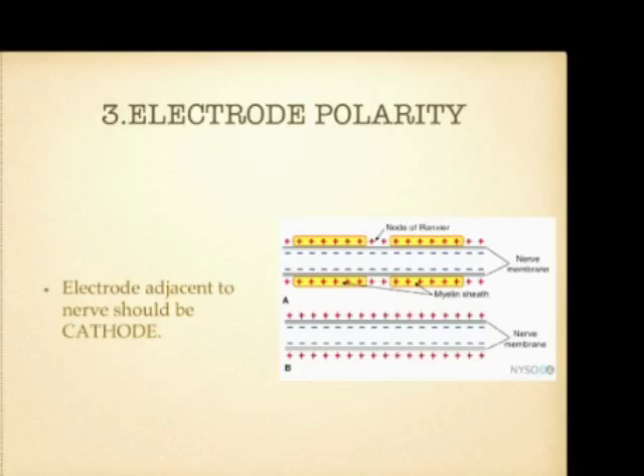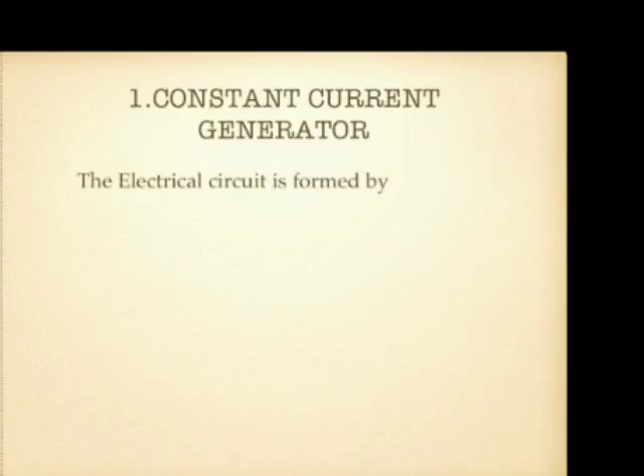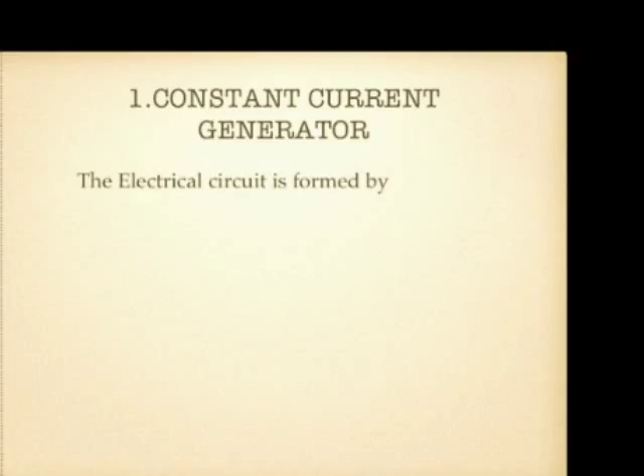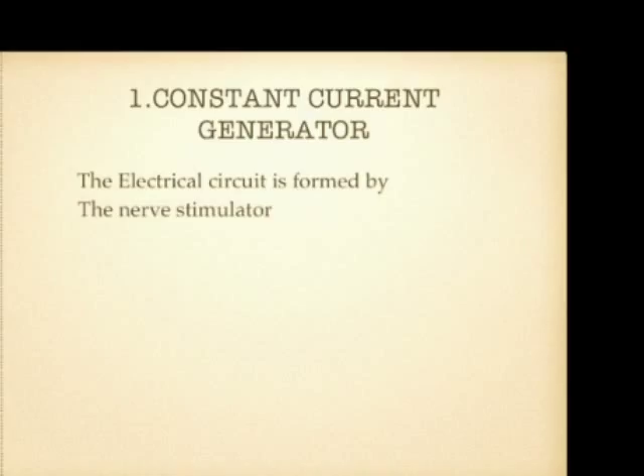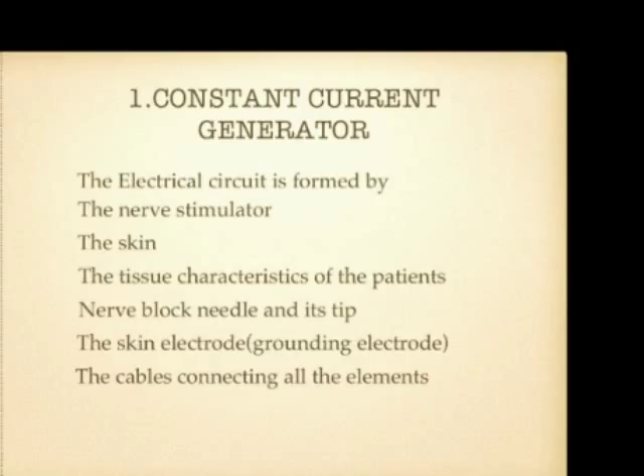For an ideal nerve stimulator, there should be a constant current generator. If you set one milliamp of current, the nerve should be stimulated at exactly one milliamp. The current delivered is influenced not only by the nerve stimulator but also by the patient's skin, tissue characteristics, the nerve block needle tip, the ground electrode, and the cables connecting all elements — all of which contribute to variable impedance. A constant current generator compensates for this wide variability of impedance, ensuring accurate current delivery and reducing the risk of nerve injury.